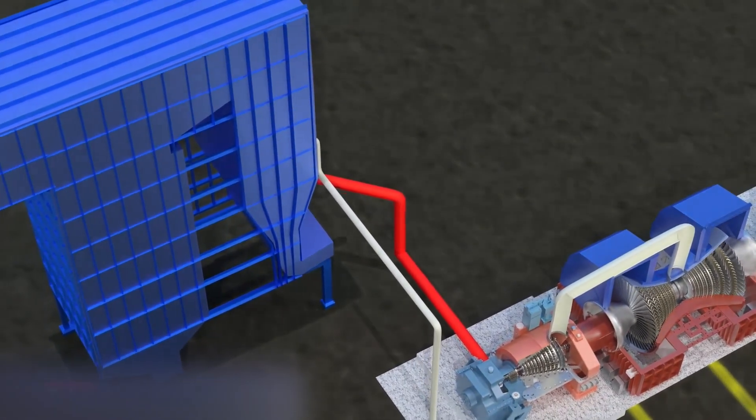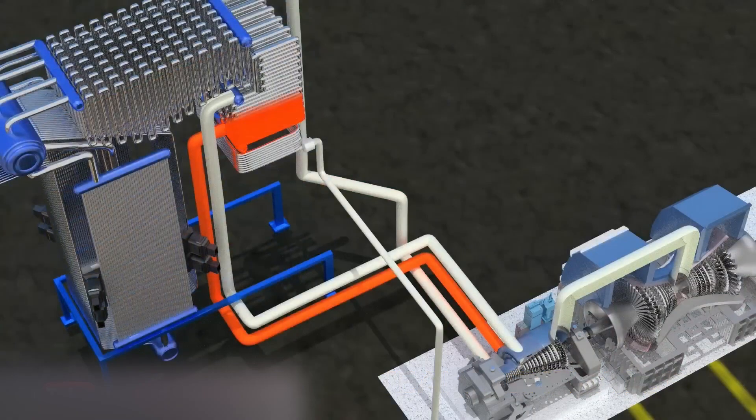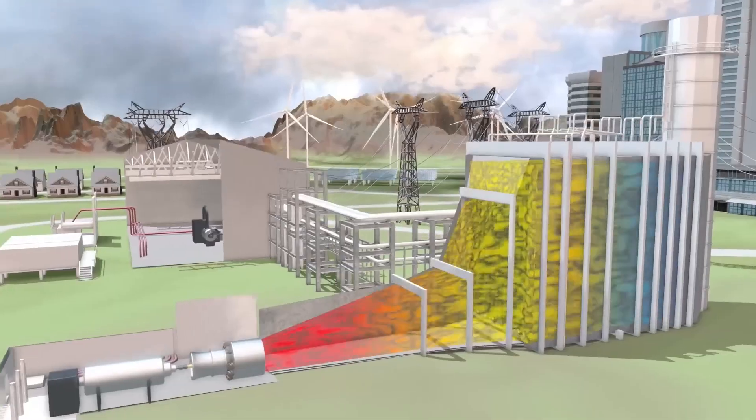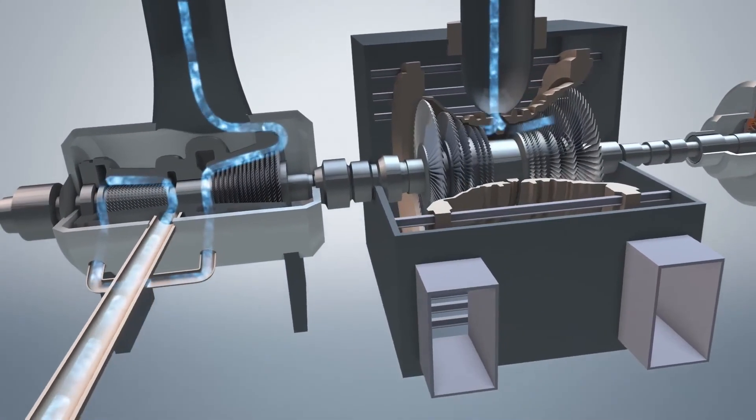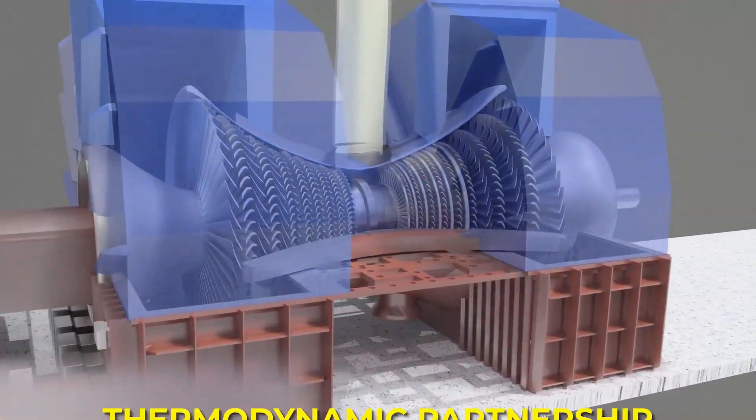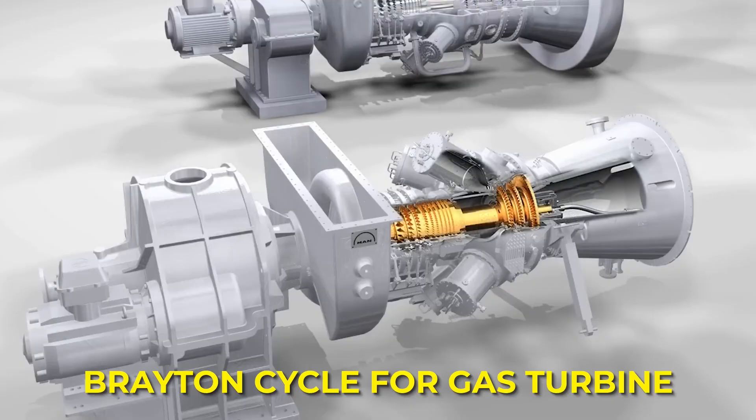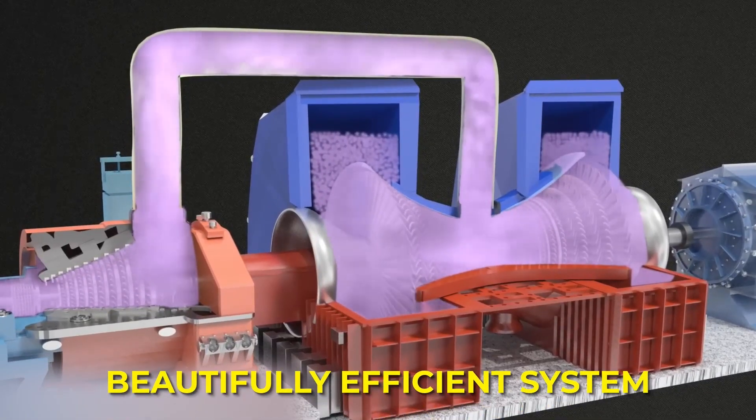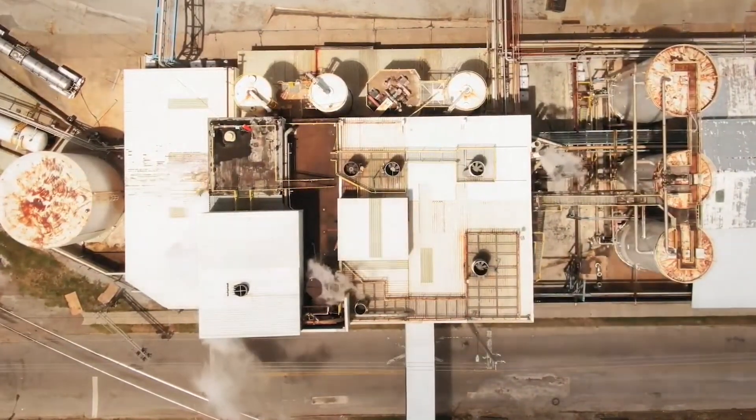In this configuration, the exhaust from the gas turbine is directed into a heat recovery steam generator, essentially a large boiler. There, the heat is used to convert water into steam. That steam powers a second turbine, a steam turbine, which drives another generator. Together, these two turbines form a thermodynamic partnership: the Brayton cycle for the gas turbine, and the Rankine cycle for the steam turbine. The waste heat from one becomes the input energy for the other, creating a beautifully efficient system.